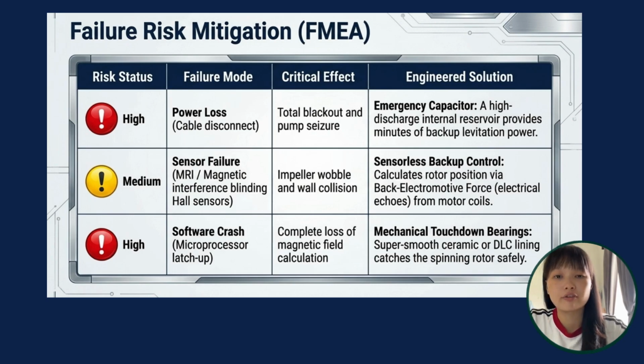Next is sensor interference or failure. The system uses Hall effect sensors to monitor exactly where the impeller is 10,000 times every second. If these sensors are damaged or confused by a strong magnet like an MRI machine or a security scanner, the pump may lose track of the impeller's position.